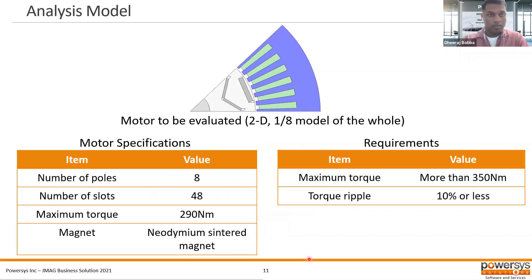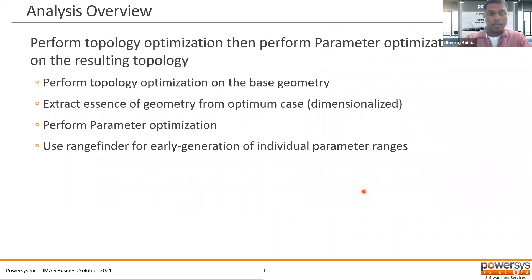This is the baseline model used for this study. It's an 8-pole, 48-slot machine with maximum torque of 290 newton meters, and the magnet is a neodymium sintered magnet. The objectives are to optimize this such that maximum torque is more than 350 newton meters and torque ripple is less than 10%. We are doing a 2D optimization, a 2D model with a 1/8 slice using a periodic boundary. The overview of the analysis is to perform topology optimization and then parametric optimization based on the optimum geometry obtained, and define parameter ranges using a range finder function.